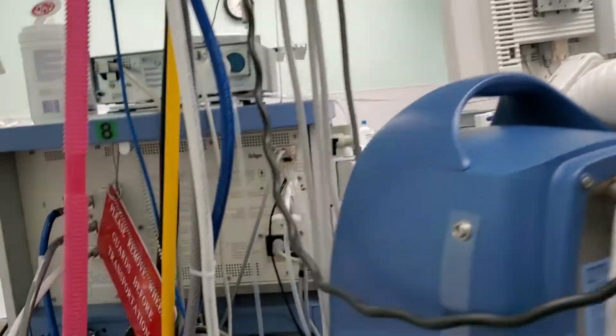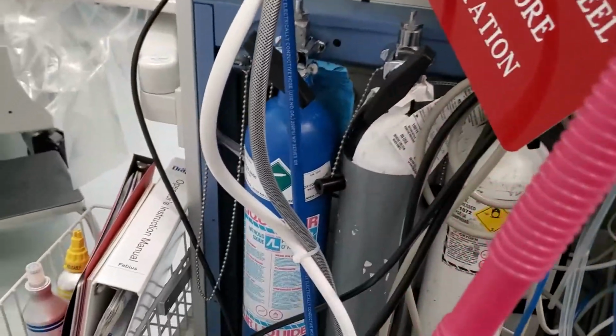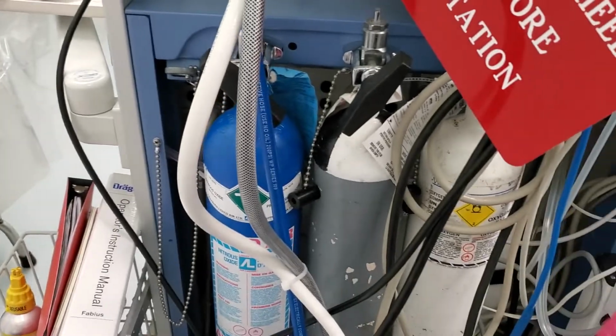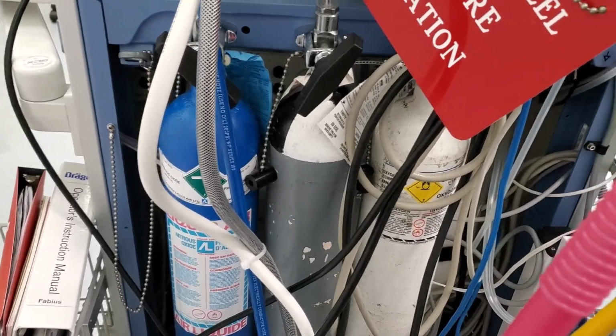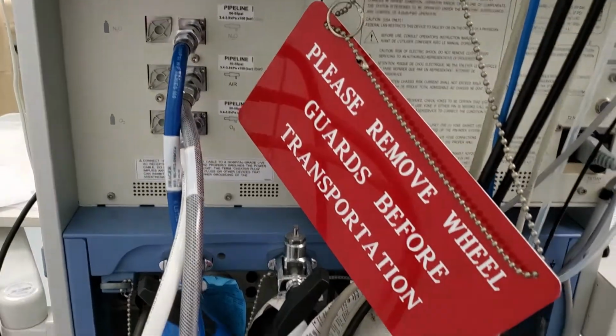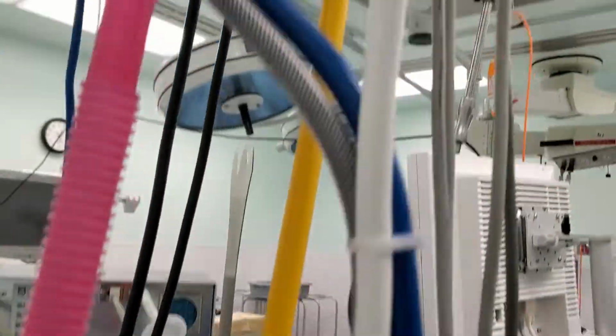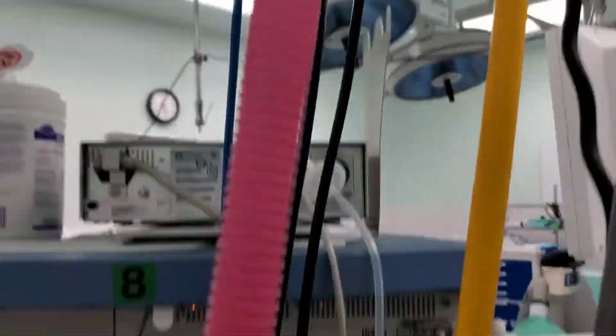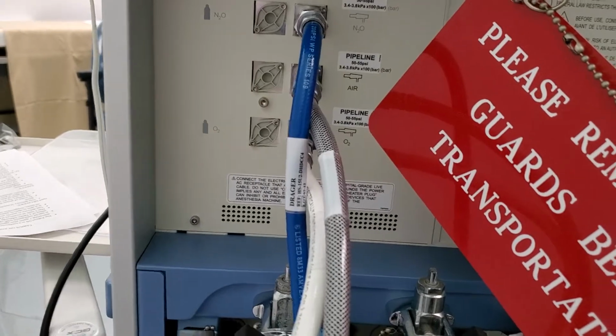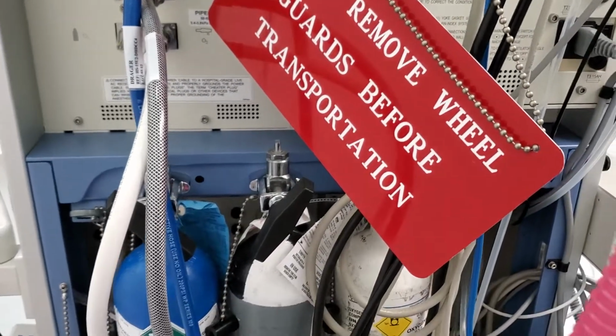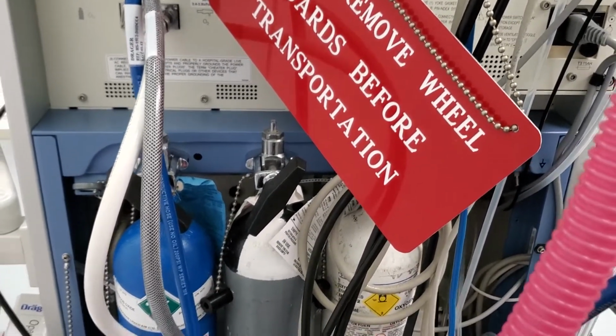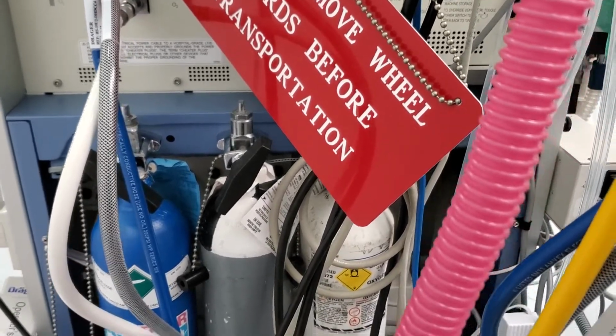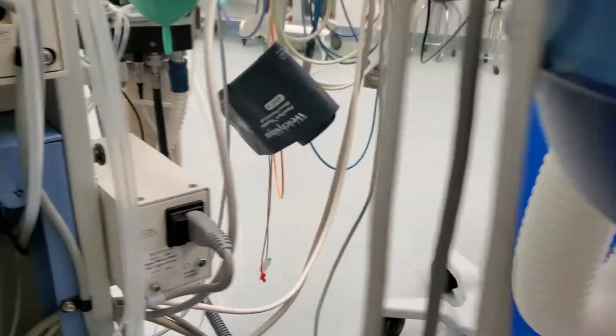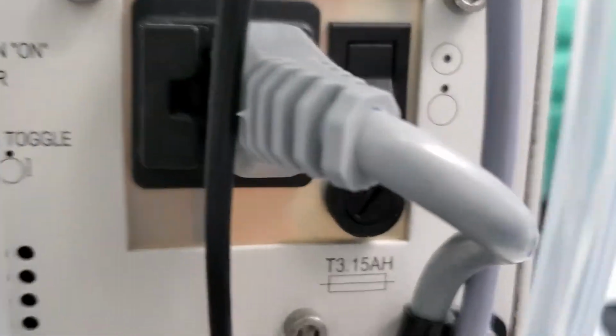We have backup tanks, so we have e-cylinders of nitrous, medical air, and oxygen. So in the event of a pipeline failure, this is our pipeline connections, and you can see where they connect to the back of the machine there. In the event of a pipeline failure, then we could turn on the tanks and have gas delivered that way. There is an on-off switch on the back of the machine here.